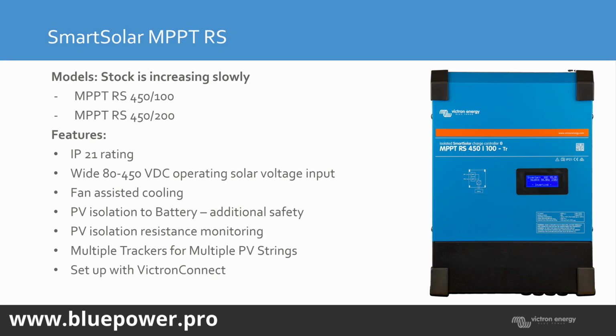And then we've got the new MPPTs also released. That's the 450-100 and the 450-200. The 450-100 has got 2 MPPT trackers, and the 450-200 has got 4 MPPT trackers built in. So you can have nice different string arrangements and orientations on the panels on the 450-200. It's got a maximum charging capability of about 11 kilowatts to the battery on 48 volts. So you can add strings from 3 panels up until 8 panels in series on these units. Depending on the panel, some can take 10.